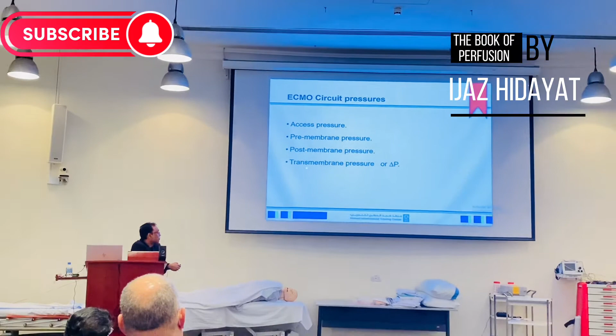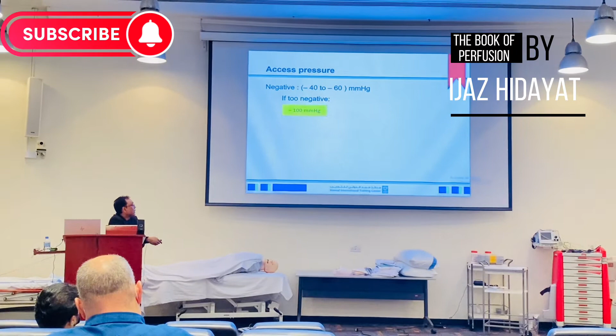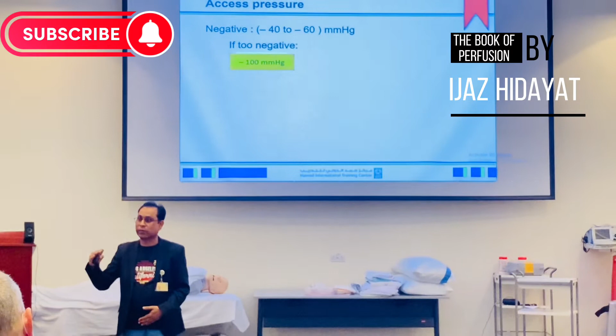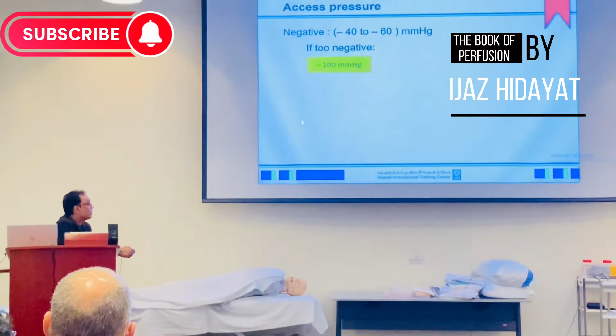So we already talked, so I am going to go through access, pre, post, transmembrane. We already talked, so we need to go. So see, what is the ideal negative pressure? What is the ideal negative pressure? 60? That's it. What should be the ideal negative pressure on access pressure? Actually, the ideal negative pressure for the ECMO is minus 60 millimeters of mercury. But normally, the cutoff for the access pressure is minus 100 millimeters of mercury. But if it goes beyond minus 100 millimeters of mercury with the higher RPM, there is a chance of suctioning and increased shear stress, which can cause destruction of the cells and hemolysis. So it should not go more than 100.